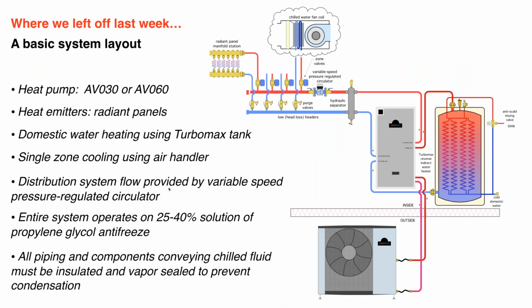And over here on the right, I'll start with the outdoor unit, the air to water unit, and then we have a glycol water solution that comes into the indoor unit. Think of that indoor unit as the hub, where we're taking energy from the heat pump and sending it out either to a domestic water heater over here on the right, or up through a device called a hydraulic separator. We're going to get into that in more detail later on.